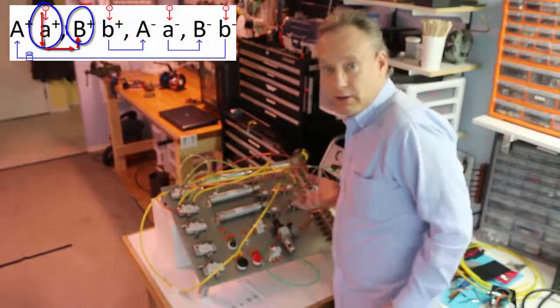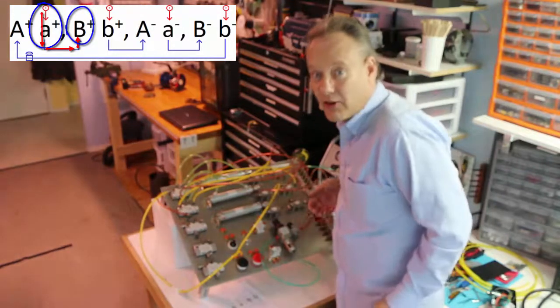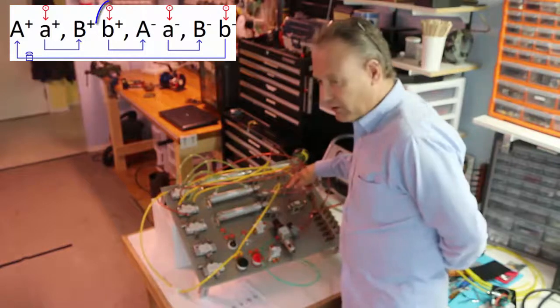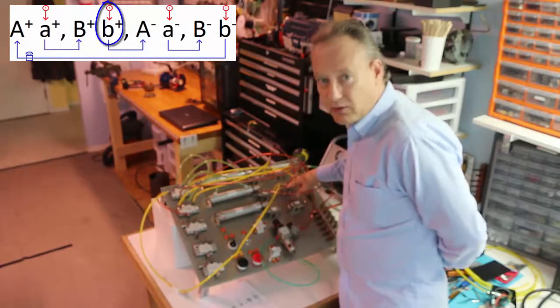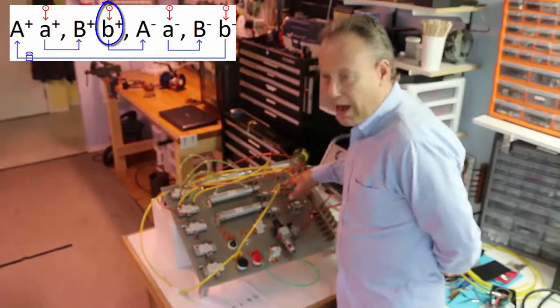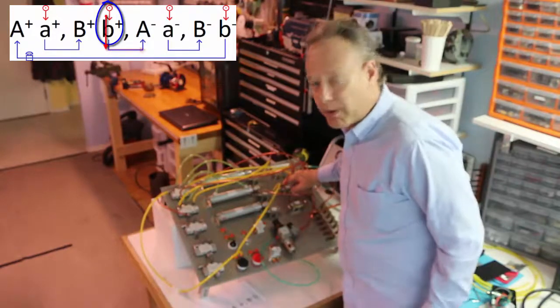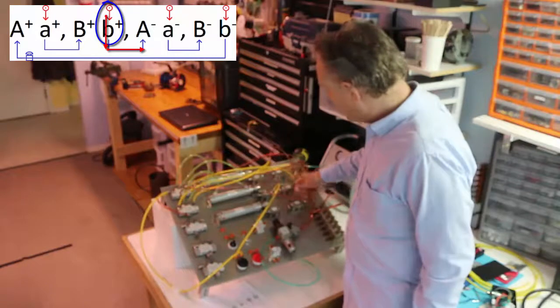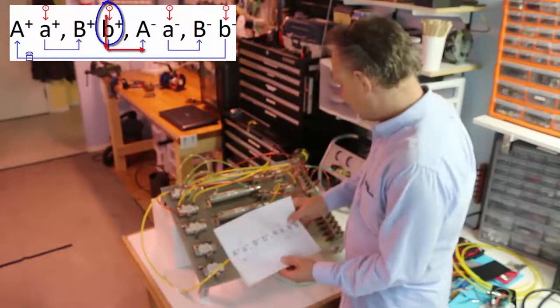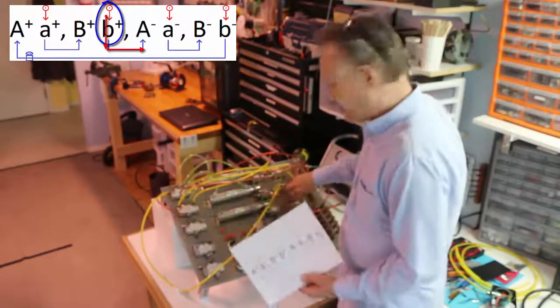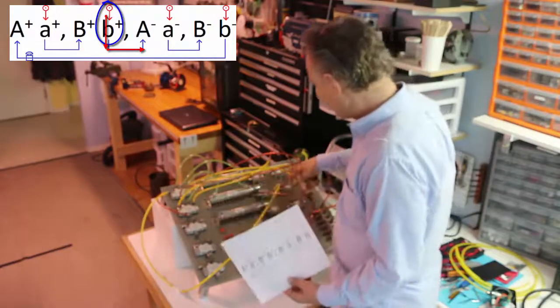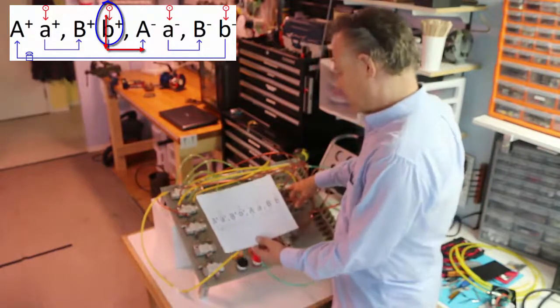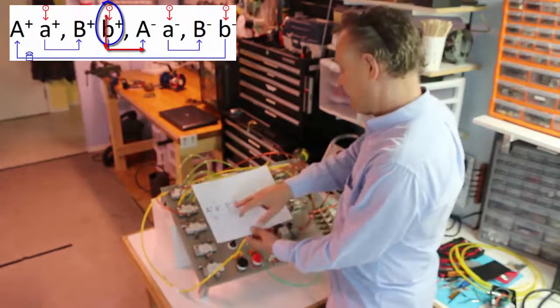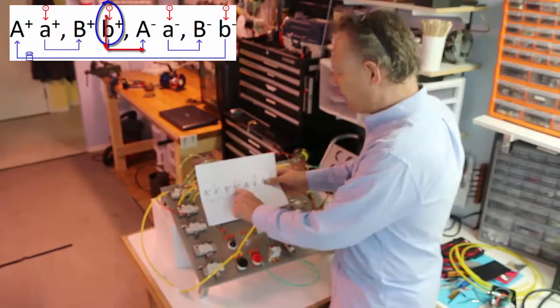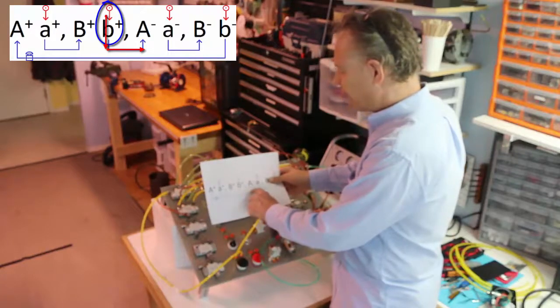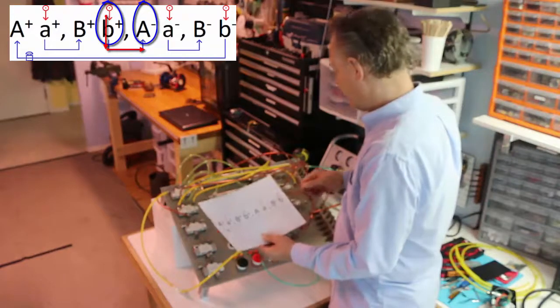When it extends, guess what? Yeah, it hits another limit valve. This limit valve is a normally closed valve. Normally, it's closed. When I activate it, it becomes open. The air, it's also got pressurized air. So actually, let's just take a look at this. Let's identify this on here. This guy is B plus. B plus is here. Okay, so it looks like the air that comes out of B plus goes into the actuator A minus. Let's take a look at that.